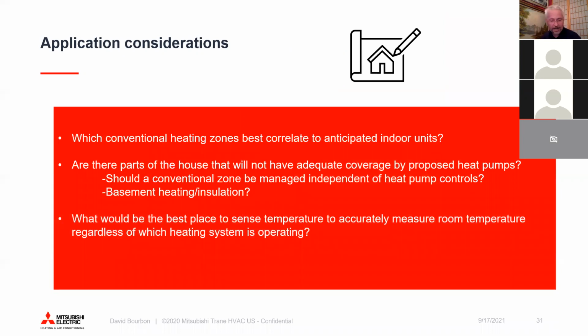So kind of coming down in closing, when we're talking about what are the things that we need to think about with applications, you need to look at the correlation between zones. What is covered by the ductless zones? What is covered by the conventional heating zones? Which ductless zone is going to be controlling whether or not this zone turns on? So if you have a conventional zone that covers an entire floor, but you have 3 ductless zones in that same floor, like a second floor, which one of those 3 zones is going to be the one that you're going to make turn on that conventional heating system? What is the mechanism or the sensing point for controlling those 2 zones? So that's one thing that you need to keep in mind.